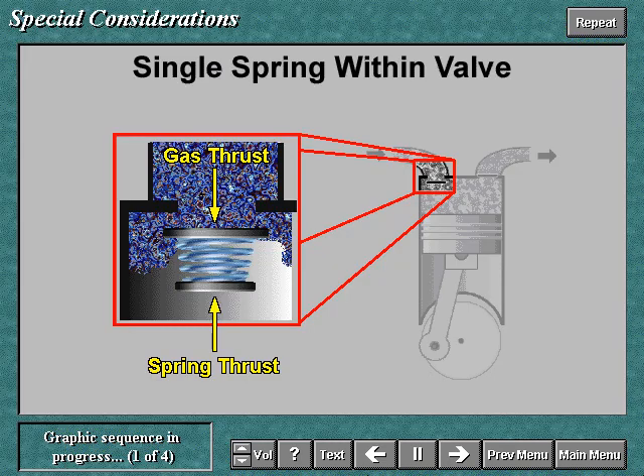The valve rings are kept lifted by the drag force due to the gas flow. They remain lifted until this force is weaker than the opposing force of the springs. The valve, however, must close just at the end of the stroke, whether it is a suction or discharge valve.